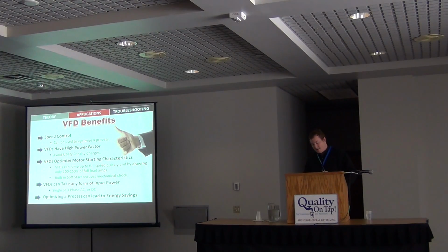I'm going to talk a little bit about soft starts here. A soft start basically has the ramp functions of a VFD without the speed modulation once we're up to full speed. So nowadays, with VFDs being as common as they are, I rarely find myself putting in soft starts unless it's an application for a motor that is always going to run full speed all the time. If there's ever a situation where it might not run full speed all the time, we typically will just put in a VFD, because then that option is available.